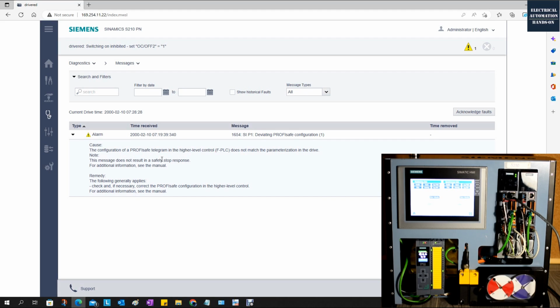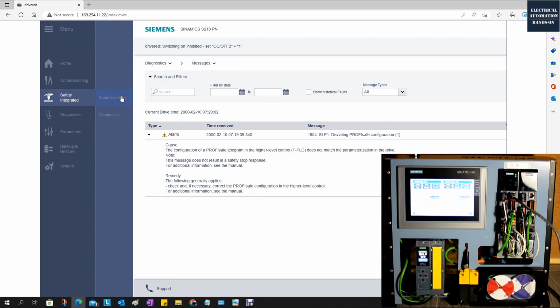But the good thing is, you can spin the motor for the testing purpose, or you can identify the motion drive direction, especially if your servo motor is connected with a gearbox, right? You don't know the mechanical direction, facing forward or backward. So you can quickly verify this. Some systems, if they have built in the safety already, without the safety enabled, you can now power on and spin the motor. That's also known in some cases. Siemens drive, by default, the safety is not enabled. So without the safety, you can still spin the motor at the initial status.